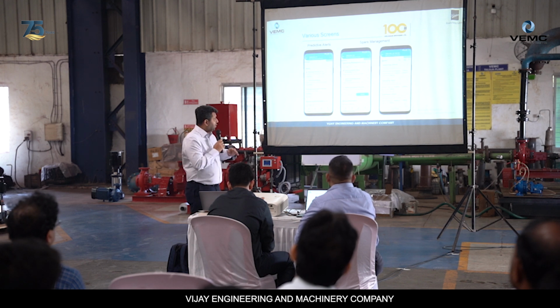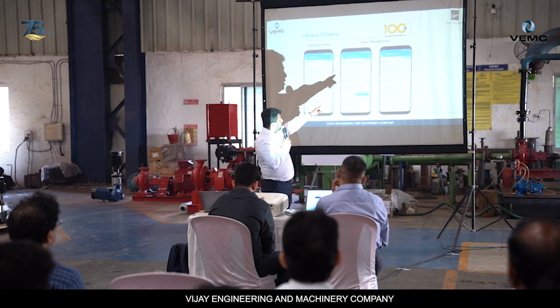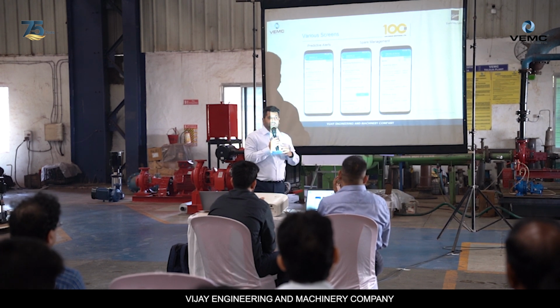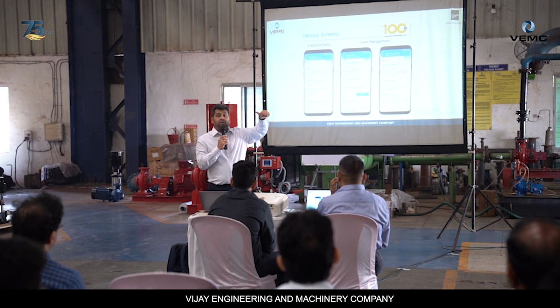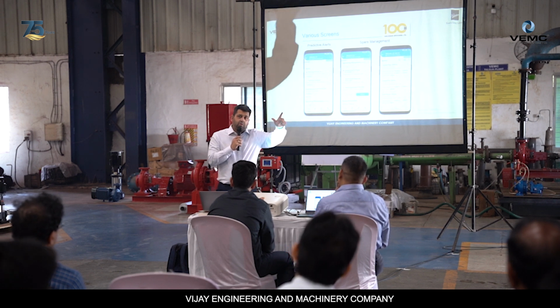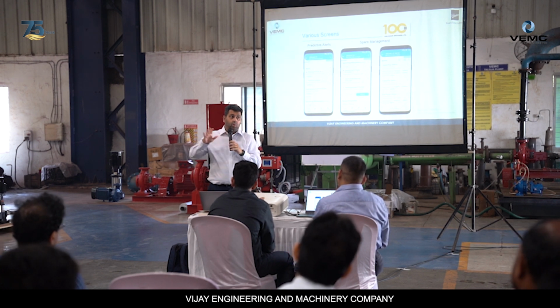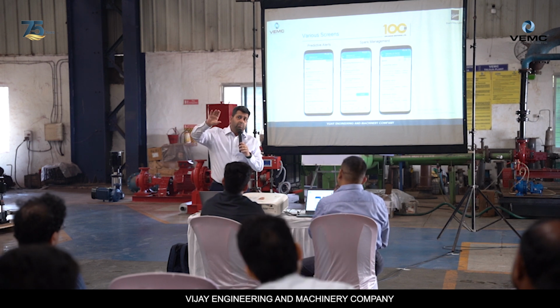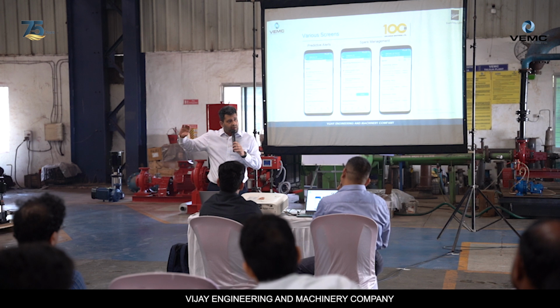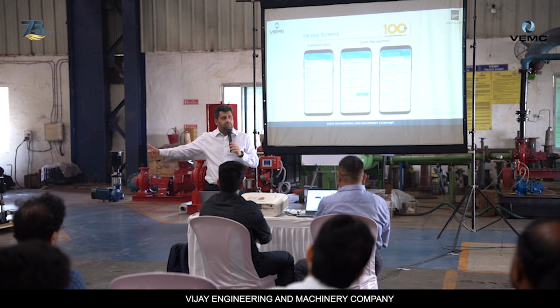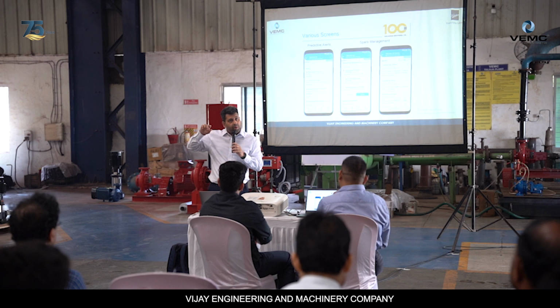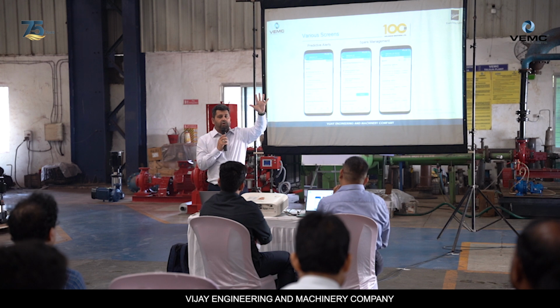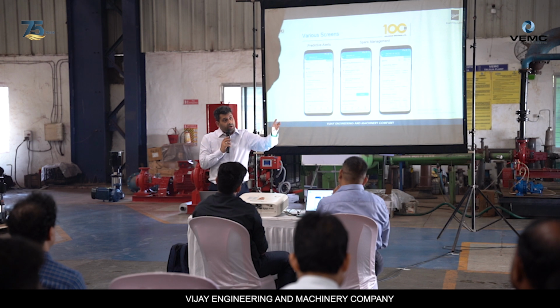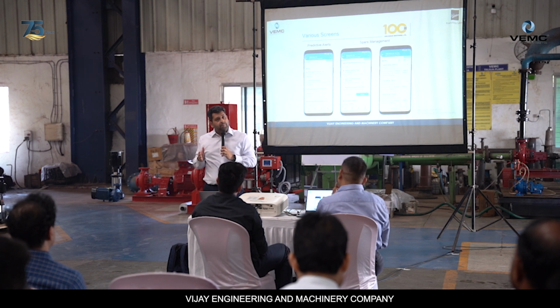Similarly, spare management - if you see the number of hours, it is already mentioned there, 8,500 hours, 6,000 hours, 7,000 hours. Now this is something we take away, it's a very important thing. In compressor business, we talk about total cost of ownership of a product, that's how we look at it. Now what they do is, they say that if I timely replace my spares, irrespective of the running hours or the years that it has to be replaced, because it's a mechanical component, then I have a higher probability that my life consistency of the product will increase. Now when we calculate total cost of ownership, we calculate it for 10 years. So similarly for pumps, we are trying to imbibe this idea that why can't you have your pumps running for a longer duration? What happens if you don't have to replace it?